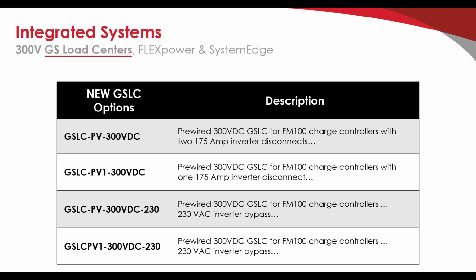The main difference is that on the new charge controller, you want to isolate the PV negative. Typically in OutBack systems in the past, the PV negative was common to the rest of the DC negative in the system. Now, by isolating the PV negative, you ensure that there's less common mode noise, electric interference on the negative, so that the arc fault device will have, like I said, virtually 0% chance of false tripping. So the part numbers won't change, but the wiring will change a little bit. There will be a direct connection from the PV negative to the charge controller instead of the common bus.